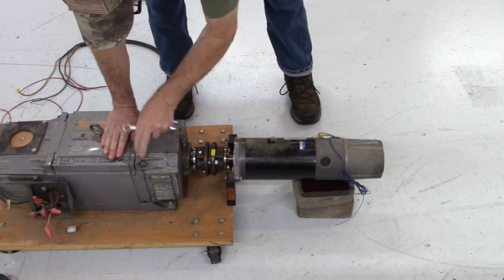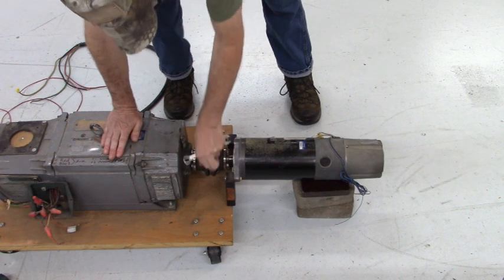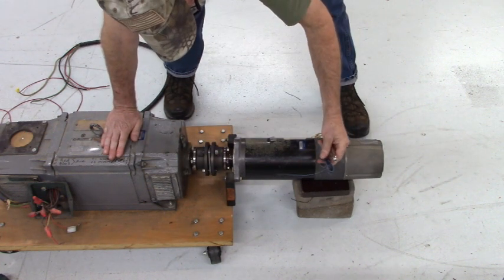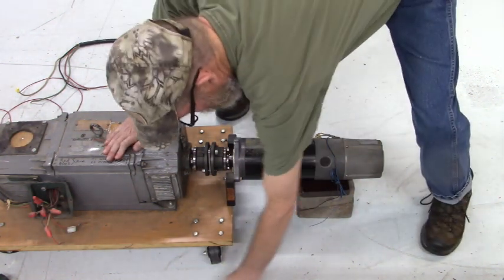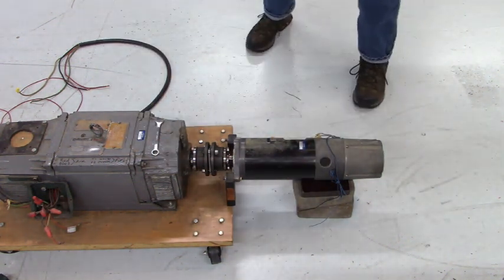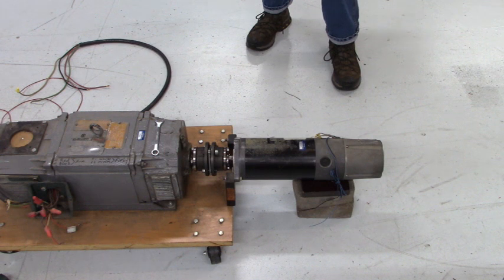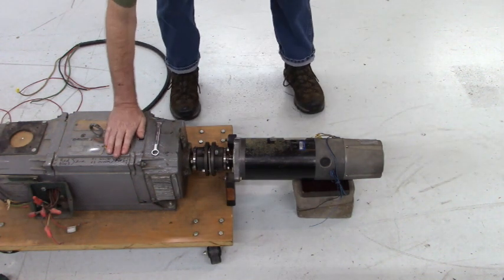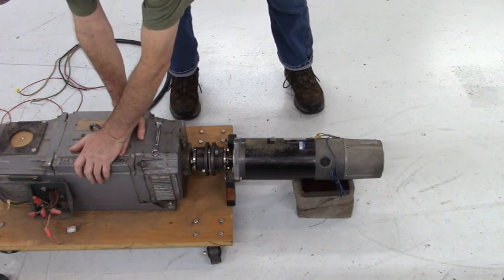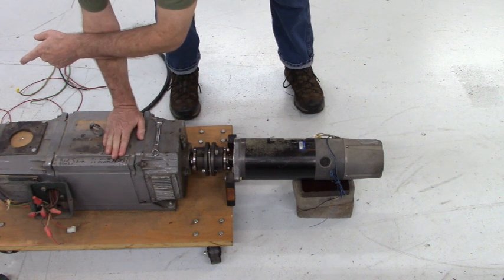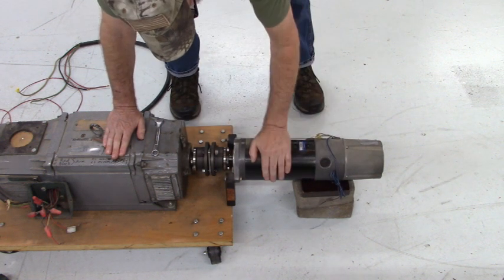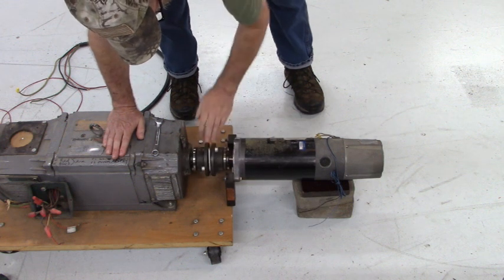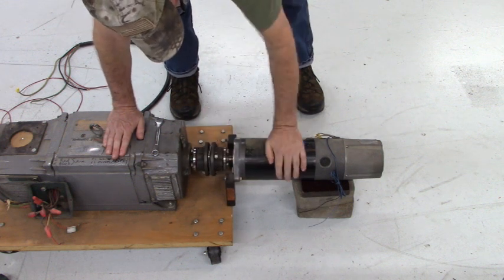And when this DC motor rotates, you will have a tach voltage from this 90 volt DC motor. There you go, that is awesome and it actually works. I've run this configuration before. I've run this motor on a DC drive with the field created from the bridge rectifier and the variac and tach feedback to that very drive with this 90 volt DC motor.